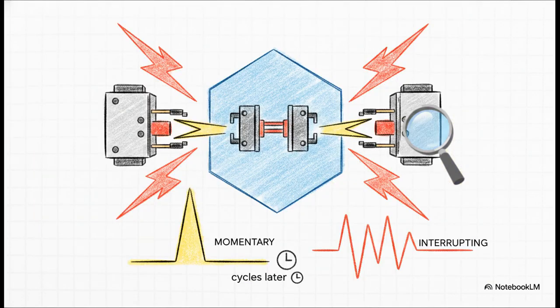Now, the real heavy hitter in the switchgear family is the circuit breaker. Unlike a simple disconnect switch, a breaker actively extinguishes massive power arcs to isolate a fault. And sizing the breaker itself is a highly precise science that uses two distinct ratings, and honestly, confusing them is a super common error. First, you have the momentary or close and latch rating. This covers the very first current peak the breaker must physically withstand without getting damaged, dealing with that highly asymmetrical peak current.